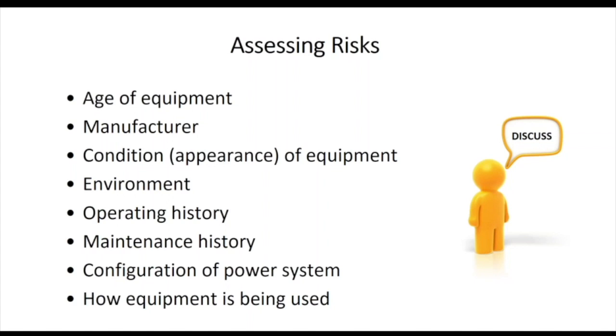What's the configuration of your power system? In the big power plants where I worked, you could switch all over - odd, even buses, tie breakers. All kinds of things will change the configuration of your power system. It'll change your short circuit current values. It'll change your arc flash values. And then how's the equipment being used? Are you running it to fail? Many, many questions. These are all risk-based questions which will affect the safety and certainly the production capabilities of your place of business.